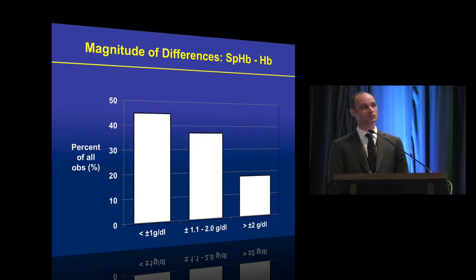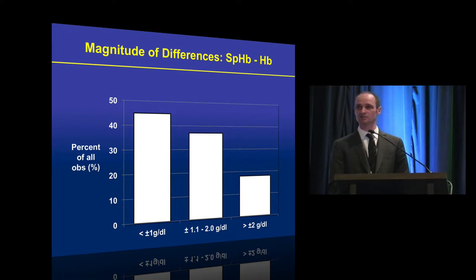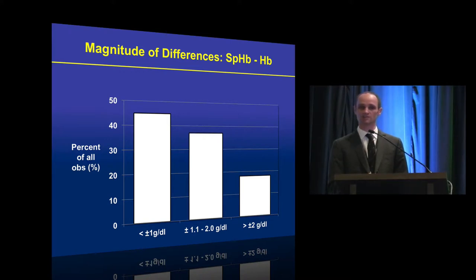We also looked at the magnitude of the differences for each observation. What we found was that in over 40 percent of observations, the difference between the non-invasive and lab hemoglobin value was less than plus or minus one gram per deciliter. However, in over 30 percent of observations the difference was between 1.1 and two grams per deciliter, and in nearly 20 percent it was greater than plus or minus two grams per deciliter. This is somewhat worrying, as it means the device can be grossly overestimating or underestimating the actual hemoglobin concentration in some patients.